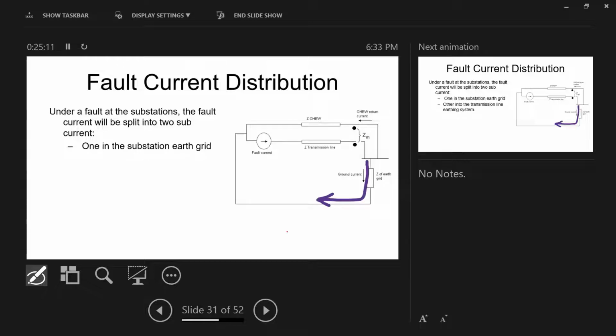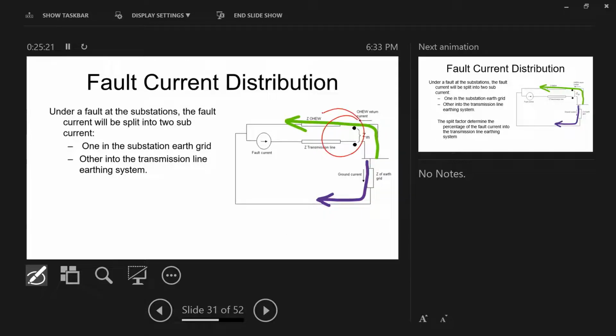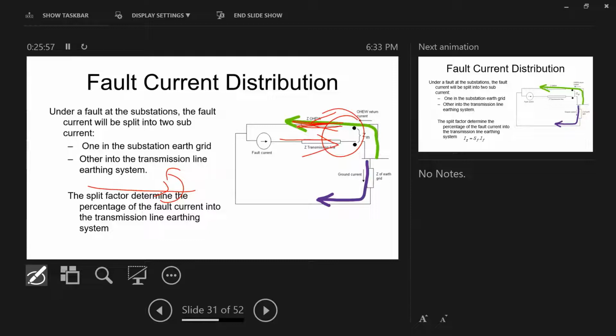When you have any fault into the ground, part of the current will go into the ground, part of the current goes back into the overhead earth wire. In the overhead earth wire, you have stuff called mutual impedance, because there will be some sort of AC interference between the phases. You have AC interference between the phase carrying the current, and you have a back EMF based on your physics. The current going through, guys, use your right hand rule. You have a magnetic field. The magnetic field will induce a voltage of opposite polarity on the overhead earth wire, and force the current to go through it. All this is governed by something known as a split factor. And this is what a split factor is.